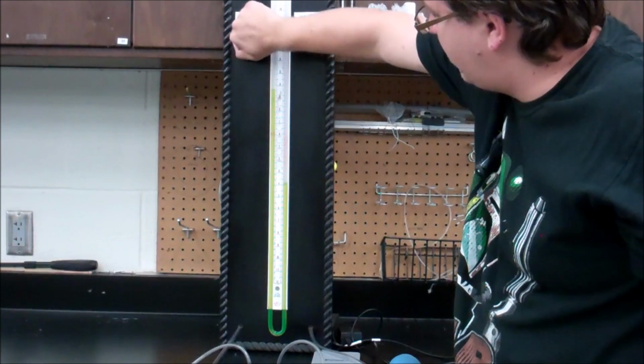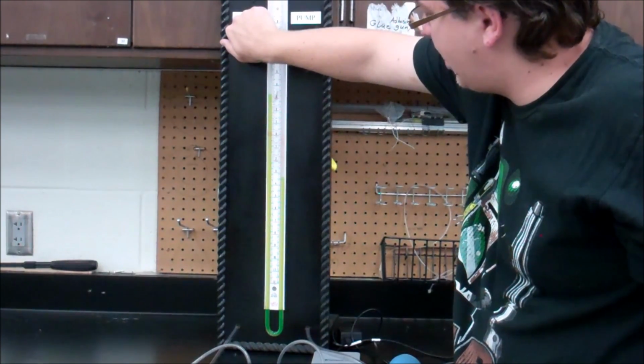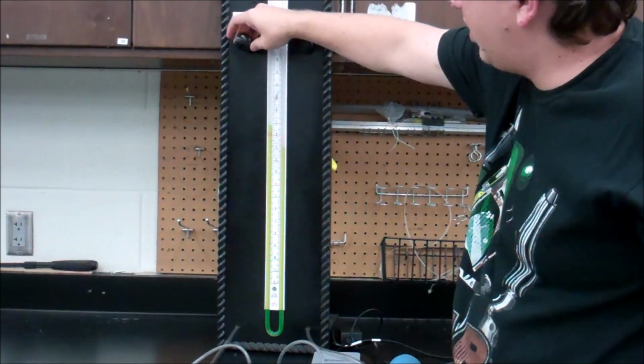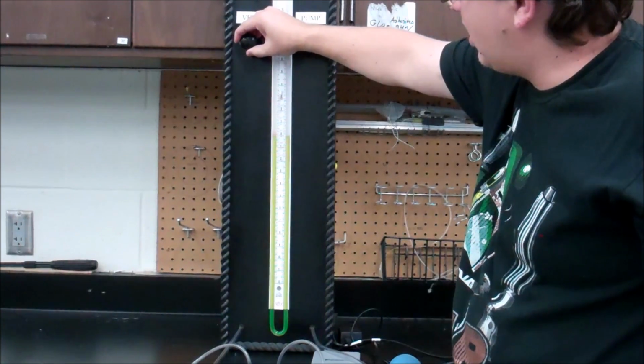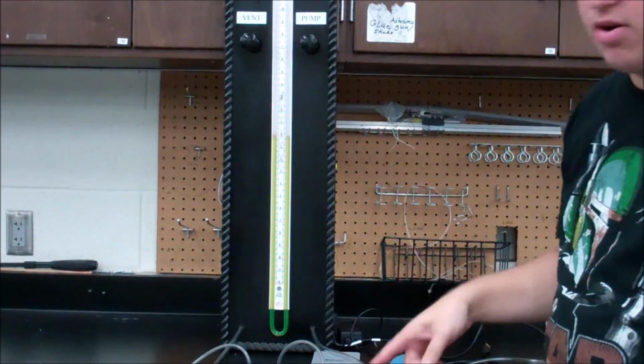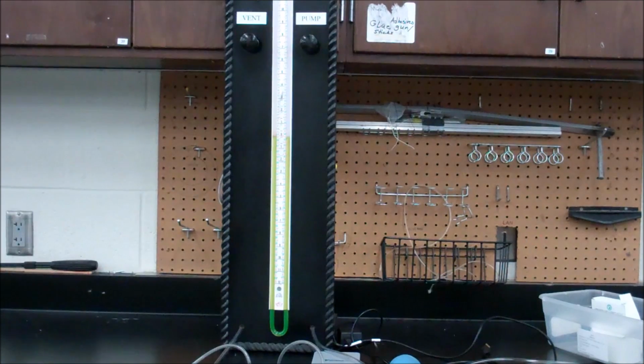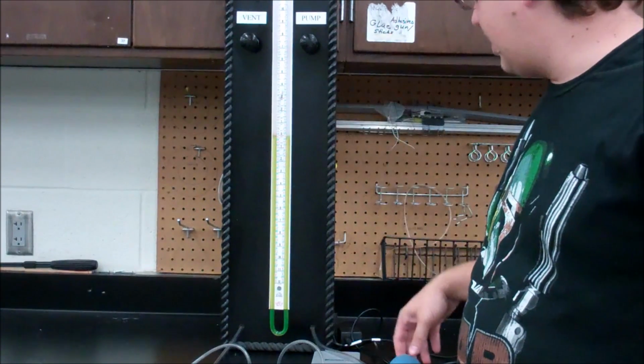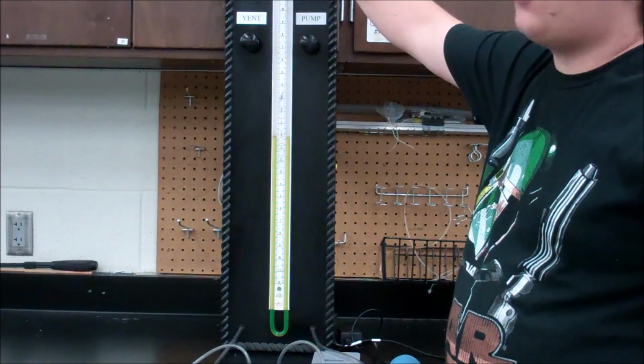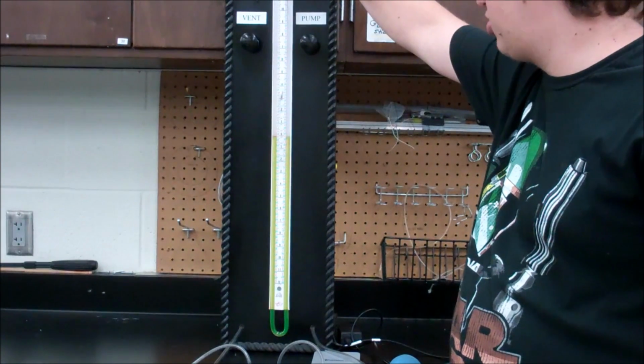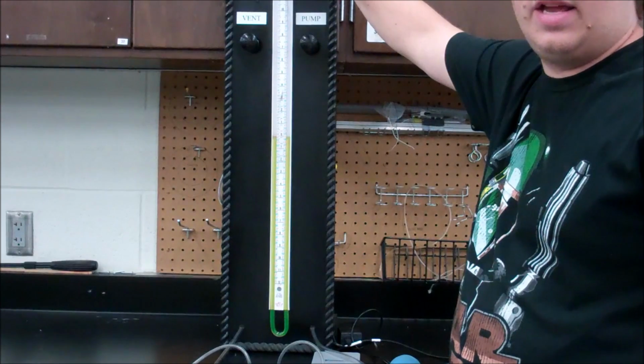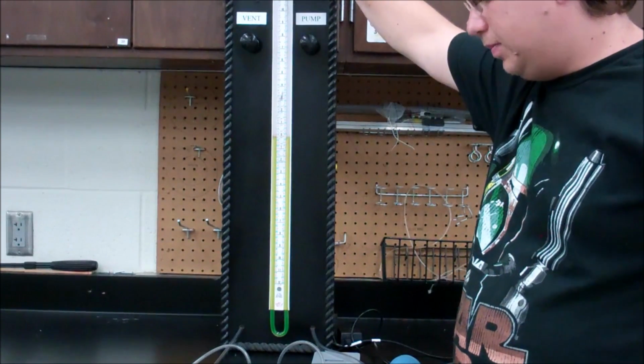And then take a measurement. Vent a little bit, get to a new height, take a measurement. And you keep on doing that until you have your 10 points. And again, make sure you get 0 as one of your points for the pressure on the low side. Now, I do not want to see any of this green liquid come shooting out the top of this manometer. So make sure you don't overpump it and that it doesn't go squirting out.